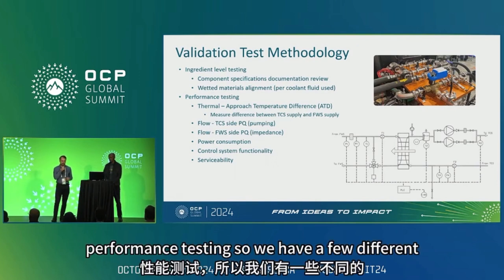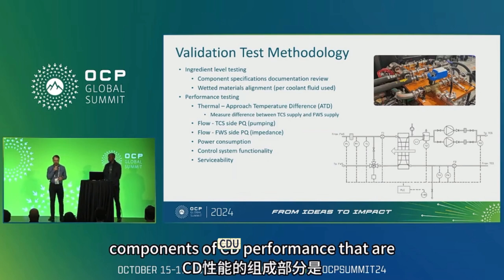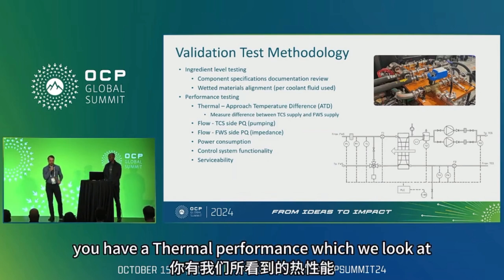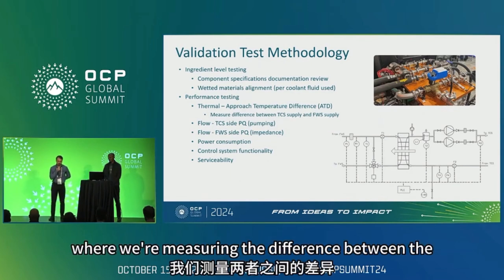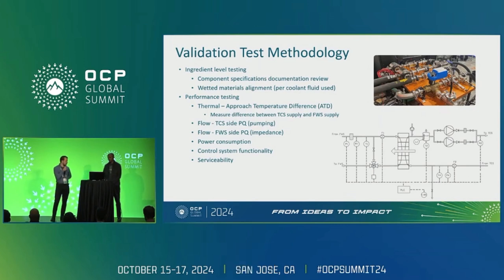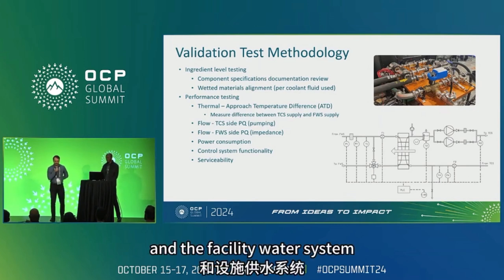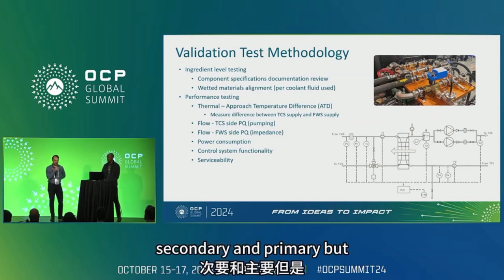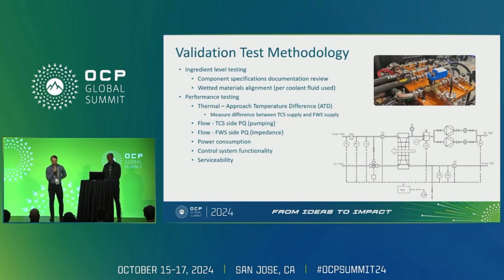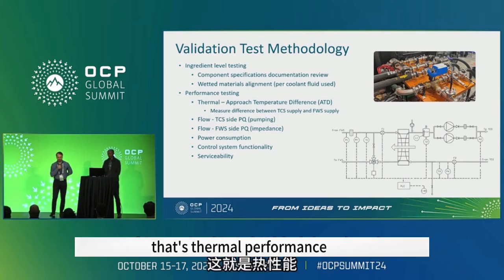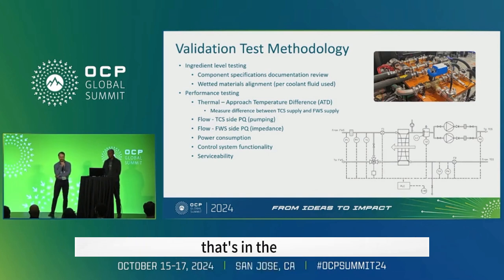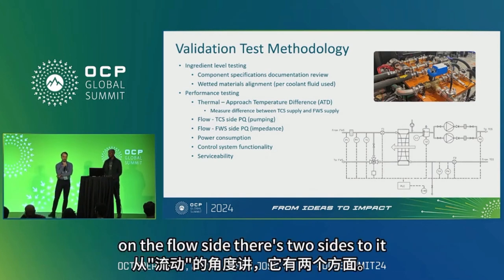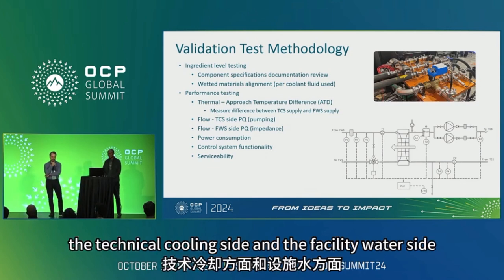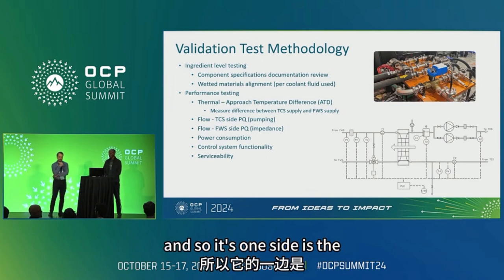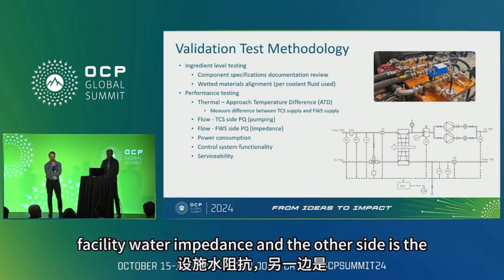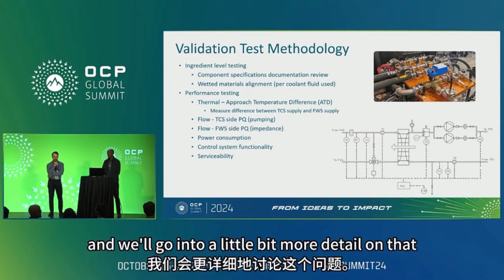Performance testing: we have a few different components of CDU performance that are pretty standard that need to be considered. You have your thermal performance, where we look at approach temperature difference, measuring the difference between the technical coolant system and the facility water system. Some of us like to call that secondary and primary, but we'll stick with that for now. That's highly related to the heat exchanger in the CDU, of course. On the flow side, there are two sides to it, the technical cooling side and the facility water side. One side is the facility water impedance, and the other side is the technical water pumping. We'll go into a little bit more detail on that.